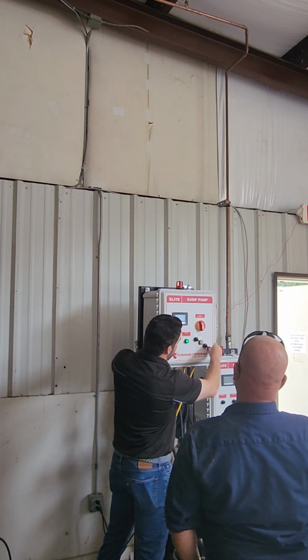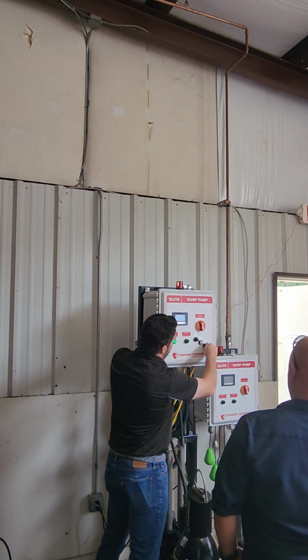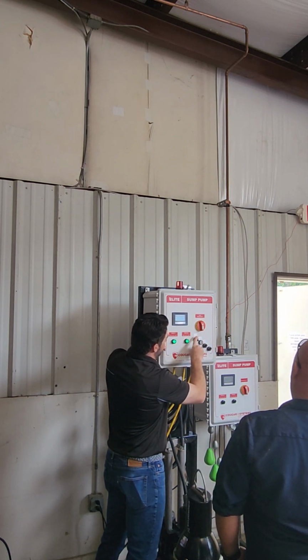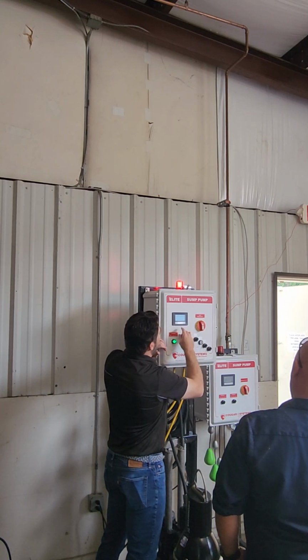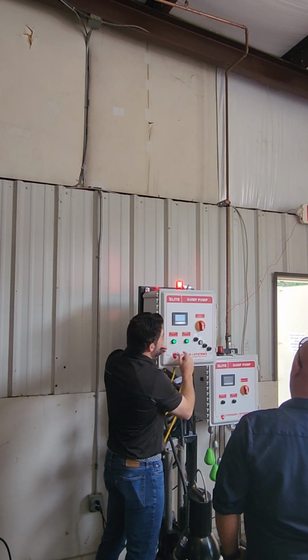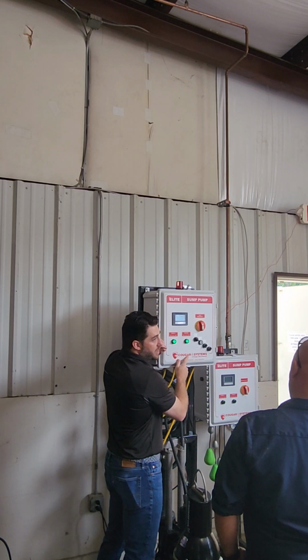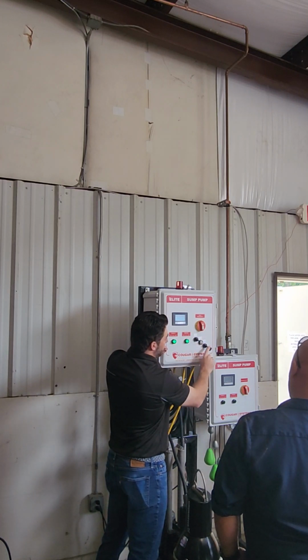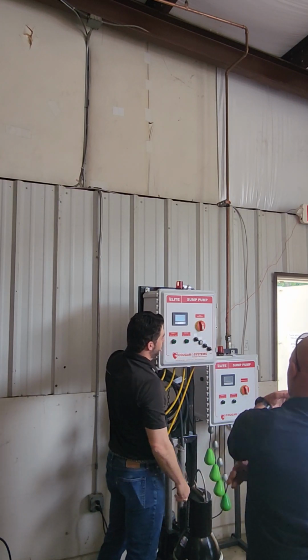All right, cool. So that pump's down and it clears. But if we go all the way up and we hit our high level, now we're going to get that high level alarm, and it's going to turn off once that top float switch goes down. Okay, but the pumps stay on until all the way down there at the bottom.